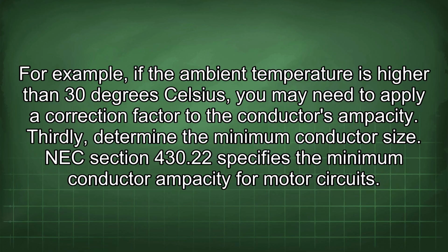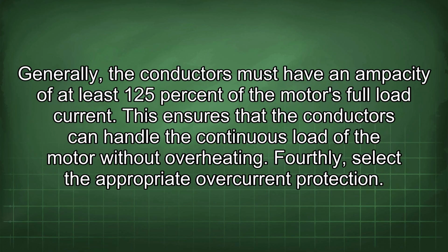NEC Section 430.22 specifies the minimum conductor ampacity for motor circuits. Generally, the conductors must have an ampacity of at least 125% of the motor's full load current. This ensures that the conductors can handle the continuous load of the motor without overheating.